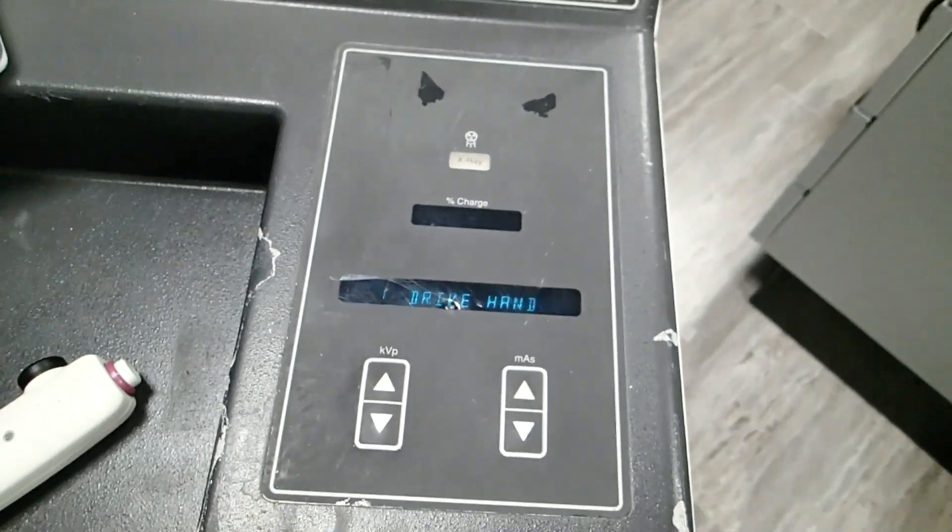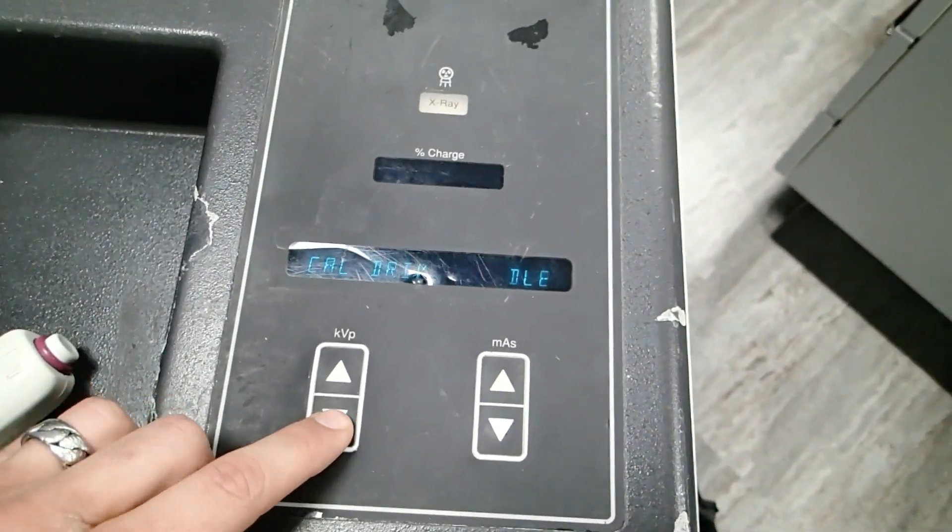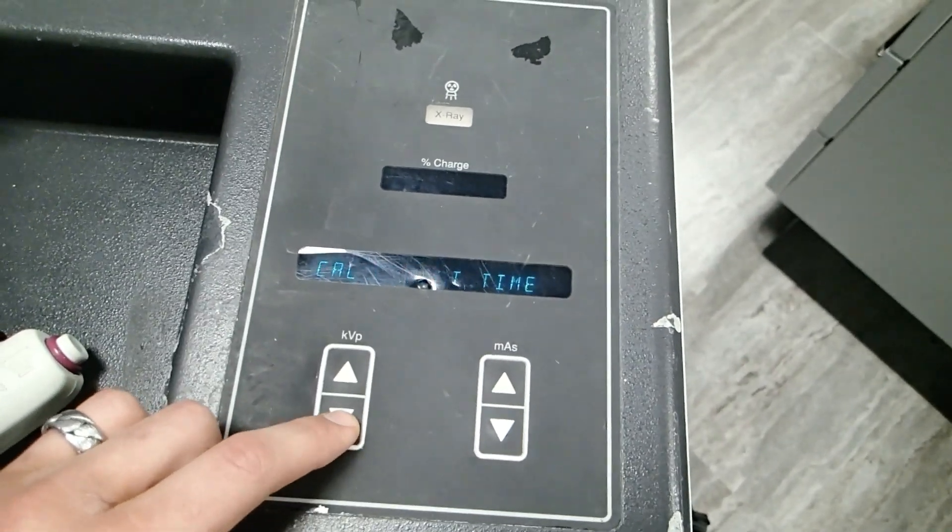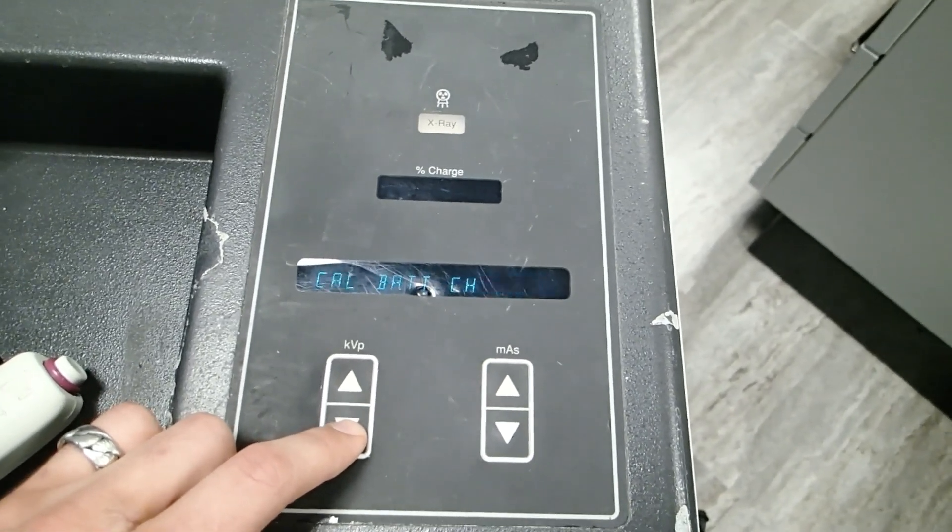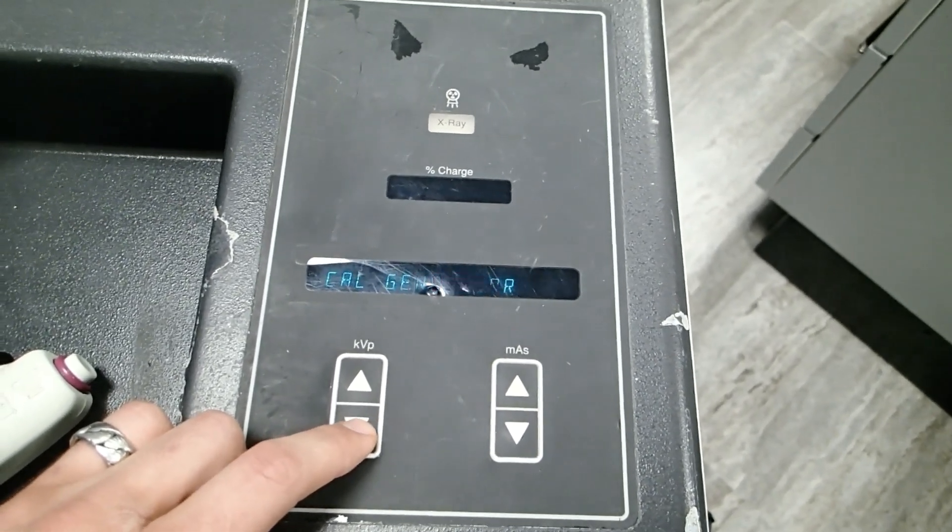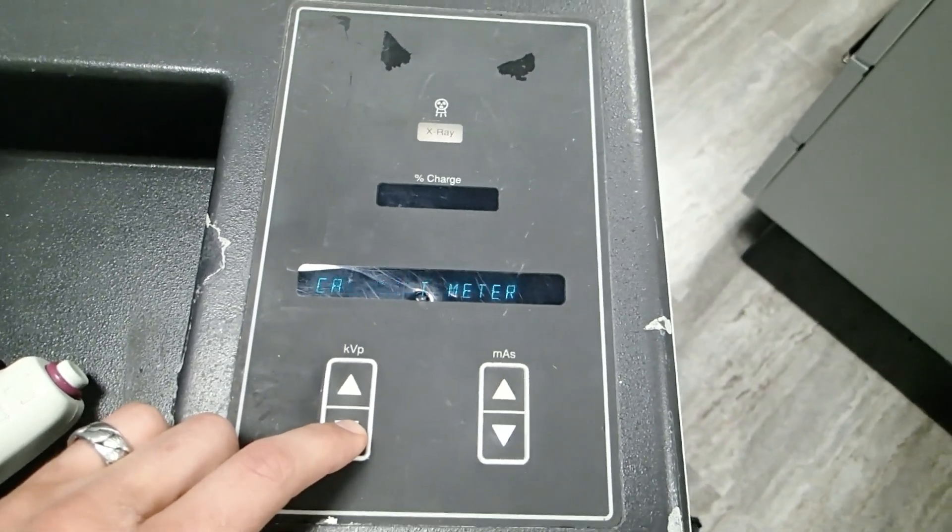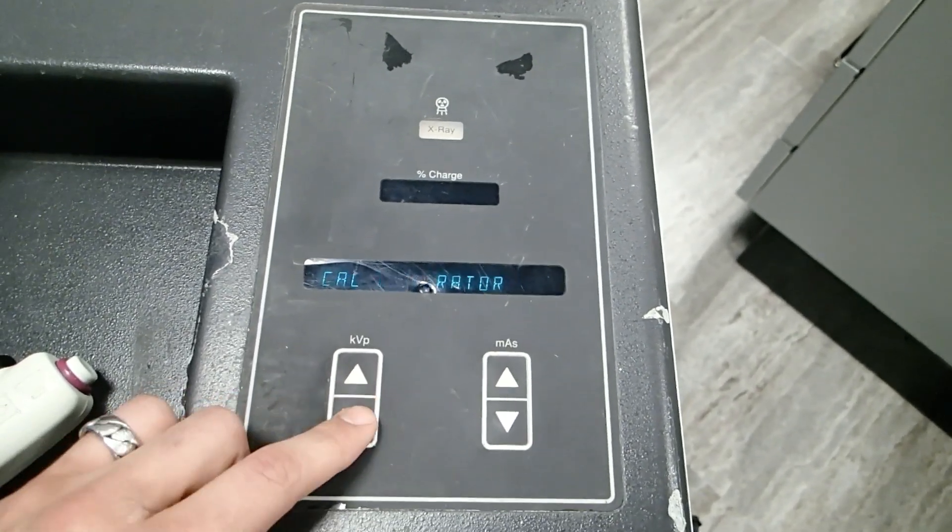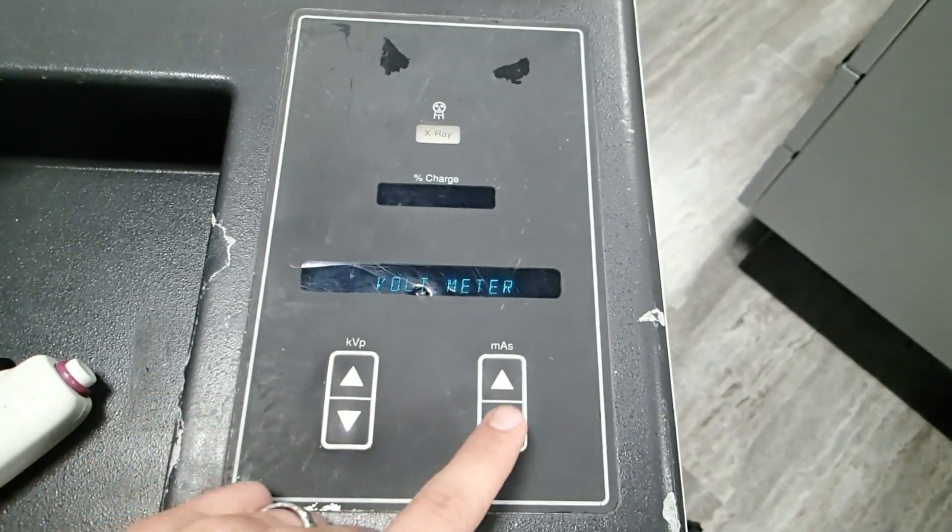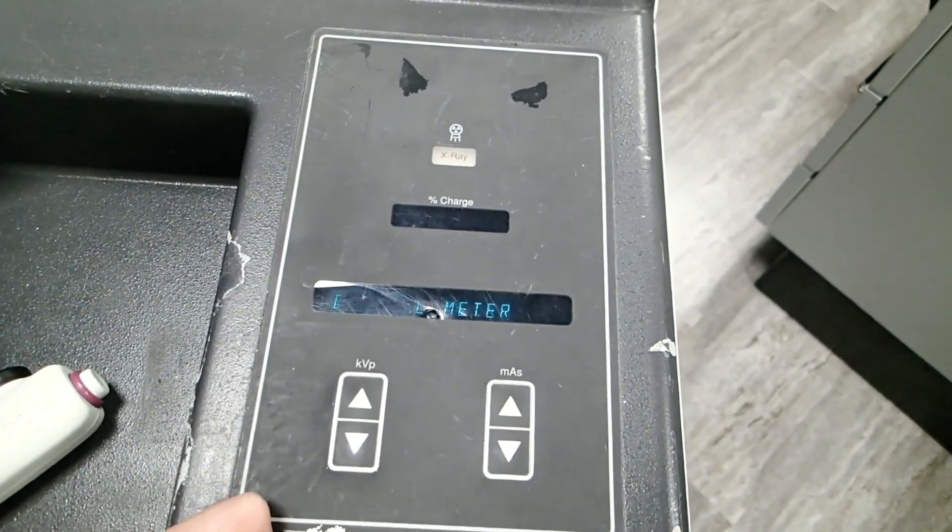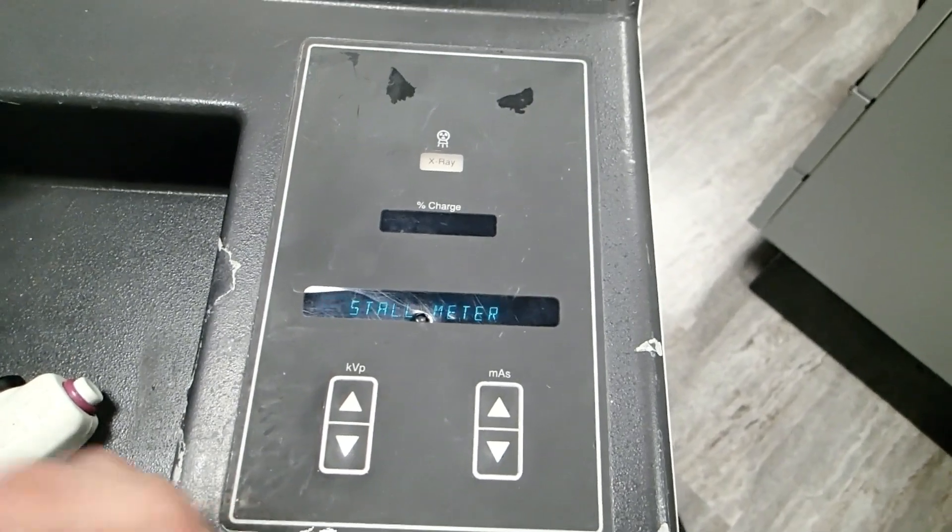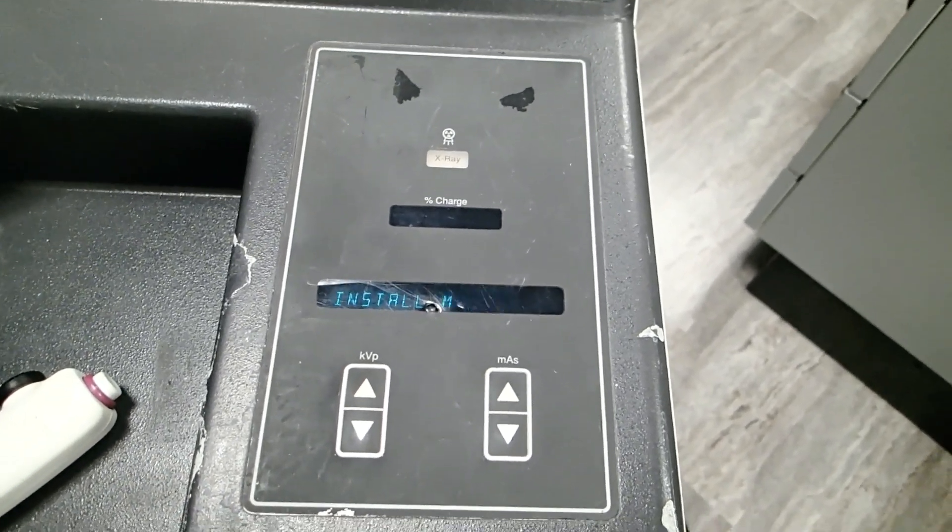Now it's asking me if I want to calibrate the drive handle. I can load default values, calibrate field light, battery charger, generator, voltmeter. We're going to start with the voltmeter and then work our way to the generator. To select the voltmeter, I'm going to hit kVp down. Now I need to install the meter.